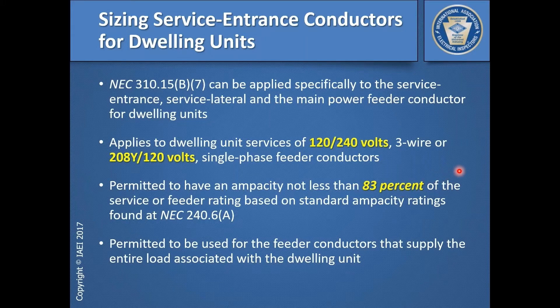You can reduce those ampacities using that 83% load calculation and come up with a smaller size service entrance conductor for a particular rating than what you might get using your standard ampacity ratings at table 310.15(B)(16). For example, let's say we had a 200-amp rated service disconnect at a dwelling unit, which is very common.